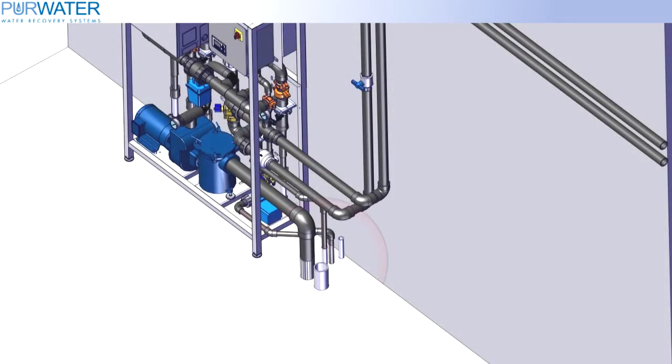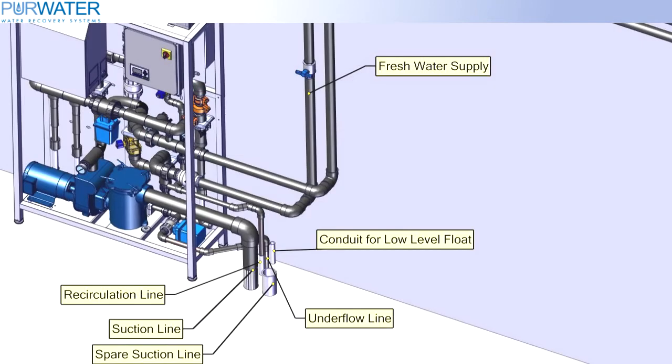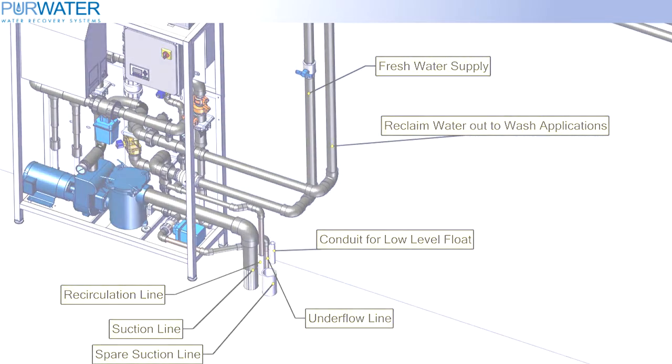All of the reclaimed plumbing should land on the right side of the reclaimed system. You will have a suction line, a spare suction line in case there is an issue with the other, a recirculation line, an underflow line, and a conduit for a low-level float connection. On the wall or close to the reclaimed system, you will need a freshwater connection, and lastly, the product water or reclaimed water line that will feed to your wash applications. Do not reduce this line size until reaching the wash equipment to prevent flow restriction and pressure reduction.